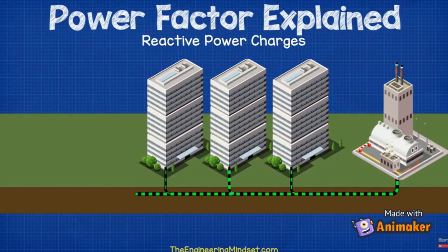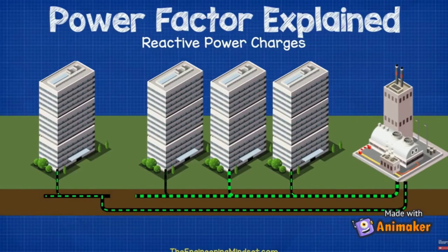Consumers with poor power factor would be penalized because they are increasing the current flow through the electricity network and causing voltage drops, which reduces the supplier's distribution capacity. Cables are rated to handle a certain amount of current flowing through them. So, if a lot of large consumers connect with bad power factors, then the cables could overload. They could struggle to meet demand and capacity agreements, and no new customers will be able to connect until they either replace the cables or install additional cables.